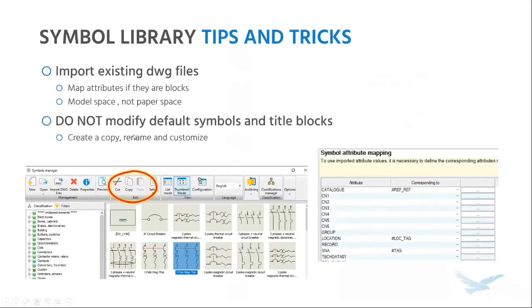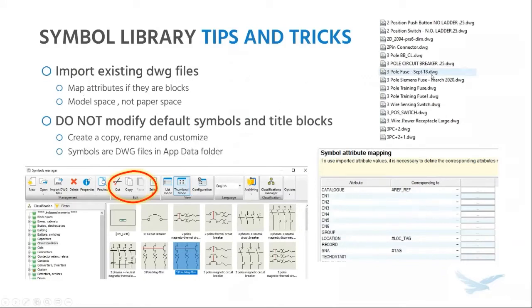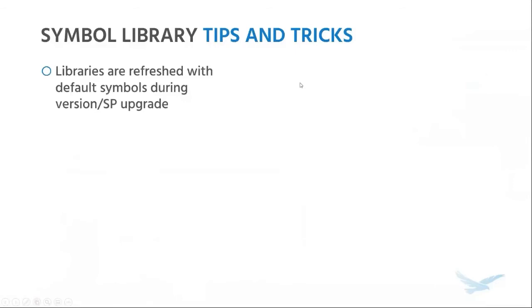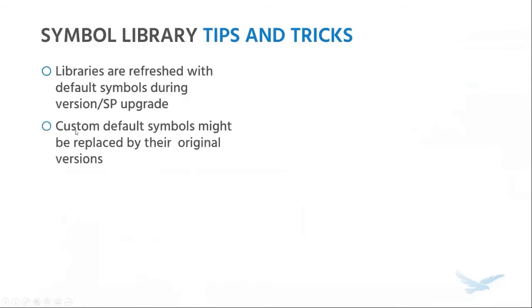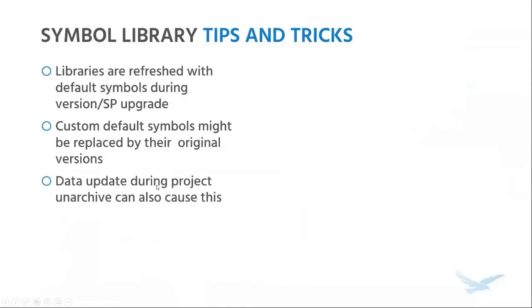Here's a big one — something I tell almost all our users: never modify the default symbols and title blocks. All the symbols that come with SolidWorks Electrical — the default symbols — if you need to customize them, do not modify those symbols. Instead, create a copy, rename that copy, and make your modifications. The reason: these symbols are DWG files stored in your application data folder. When you modify a certain symbol, you're essentially modifying that file in the app data folder. Where this could be an issue: if you're performing a version upgrade or service pack upgrade, SolidWorks Electrical will try to refresh your library with the default symbols — so all the default symbols you've been customizing might be replaced by their original versions. This could also happen if you're running the data update tool when unarchiving a project.